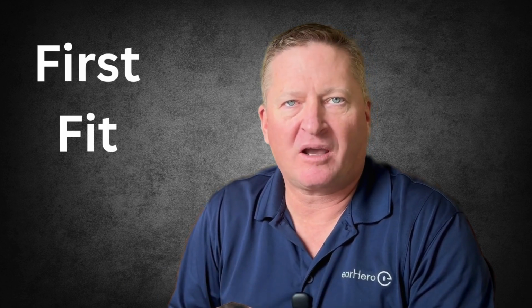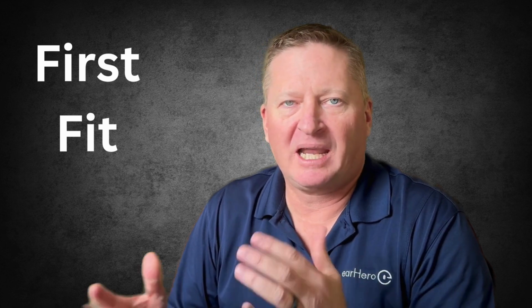Most hearing aids start with something called the first fit. That's where the software uses your hearing test, your age, and an average ear model to calculate the settings determined by the device manufacturer. First fit can get close, and the provider can make this sound really impressive, but here's the reality: first fits are almost always wrong. They can be off by as much as 10 or 15 dB, maybe even more. That may not sound like much, but in hearing it's massive. Depending on the frequency, too soft a sound can mean speech is unclear, and too loud a sound can mean everything is harsh and tinny. And without real ear measurements, no one truly knows how the hearing aids are meeting your prescription.